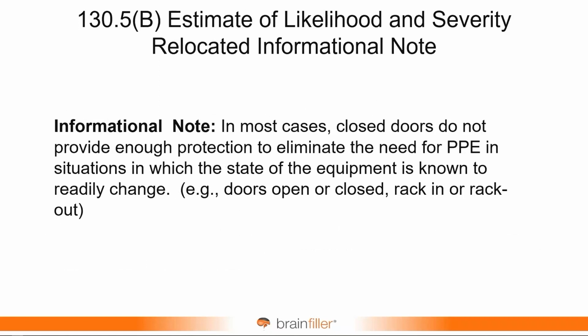We have an informational note that states, in most cases, closed doors do not provide enough protection to eliminate the need for PPE. In fact, when you perform an arc flash study, incident energy analysis, IEEE 1584, the calculations based on that standard assume that there is no door, that the door is wide open, because you just don't know. Unless the equipment is specially designed to keep the door closed and contain the energy, like arc-resistant equipment, you don't know if the door is going to stay closed. It might, but it might not.